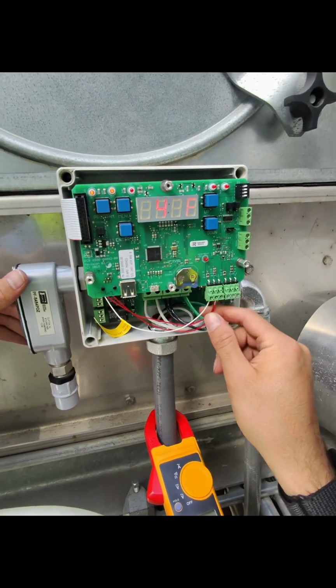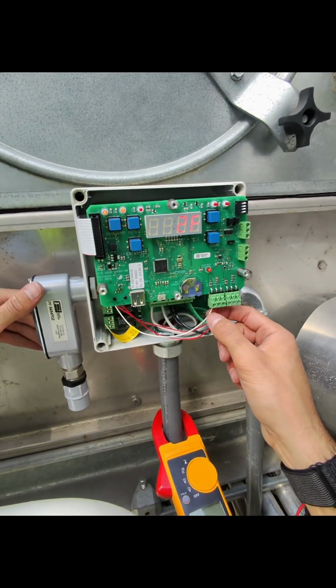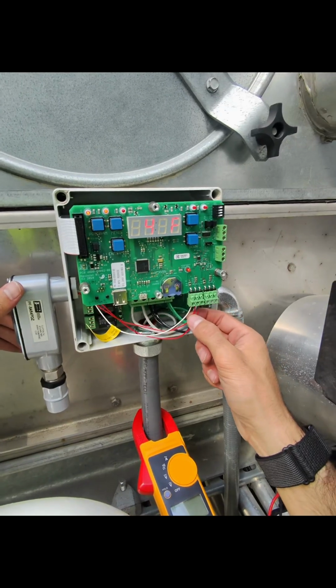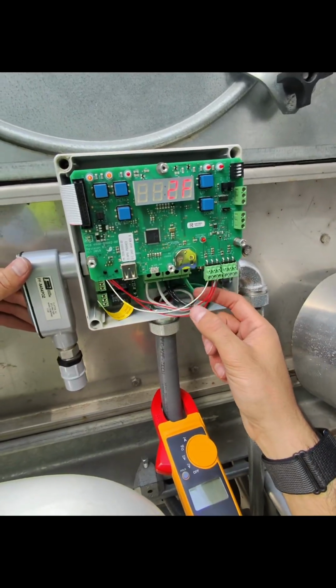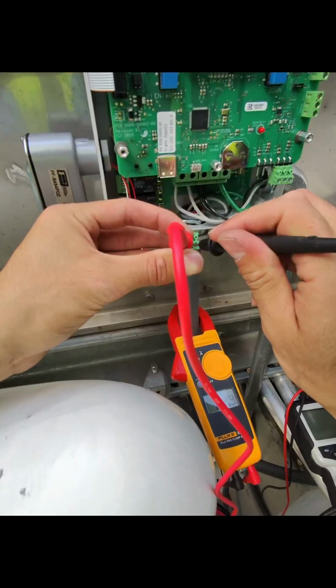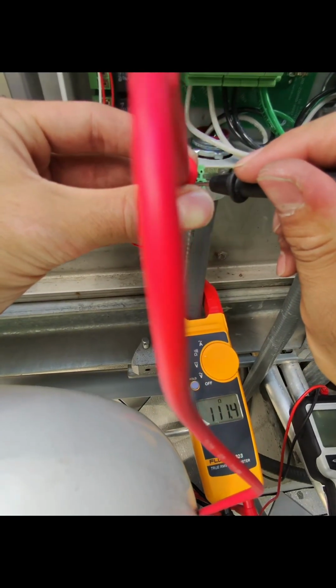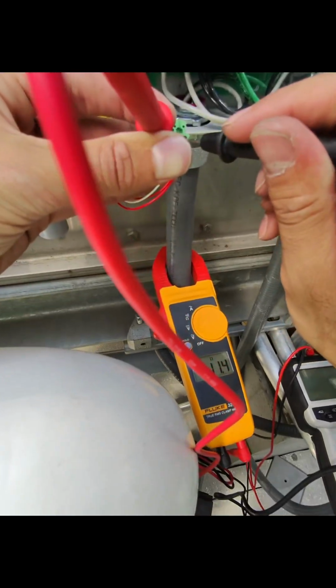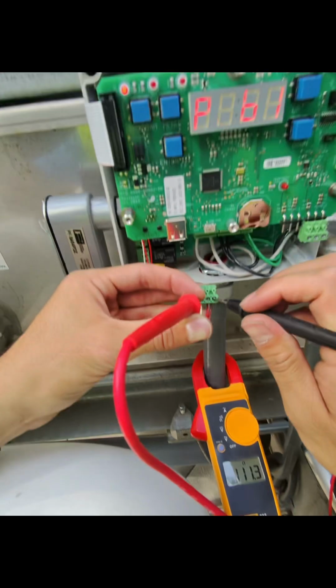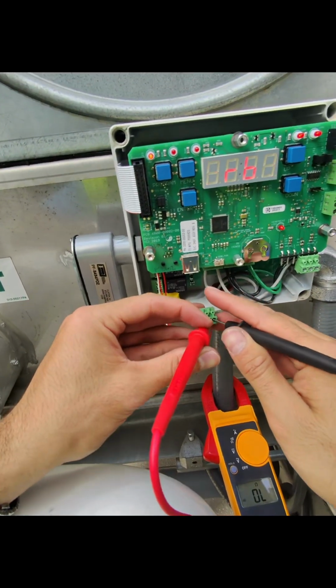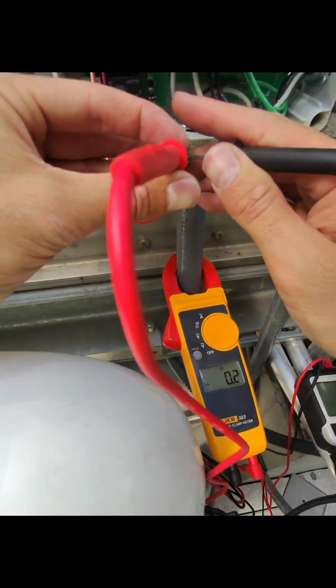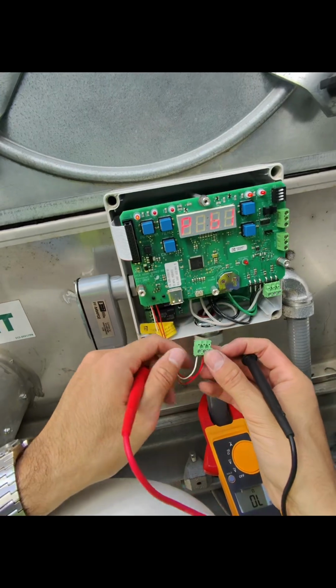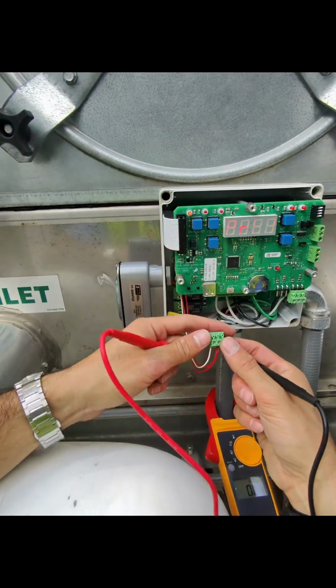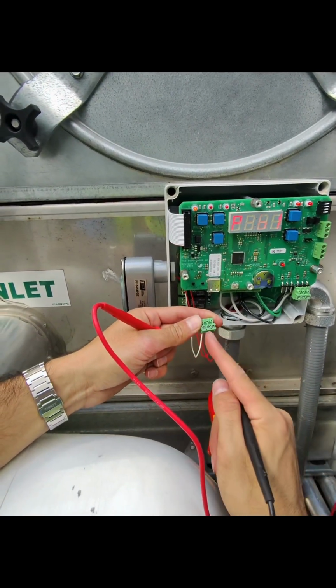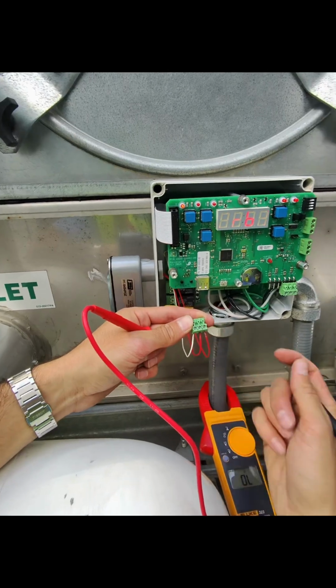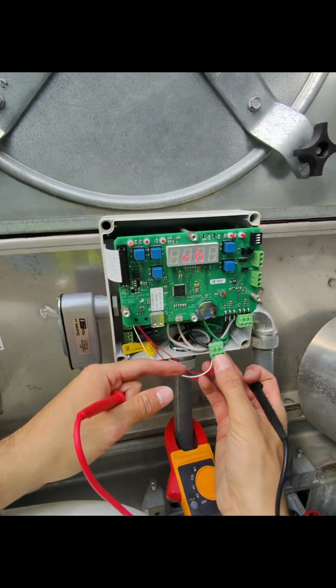The way you can test this, if your wires are not white, red, red, say you're using an extension wire or something similar, you would take a resistance reading. So from white to red, I get 111. From white to red, I get 111. And then from red to red, I get continuity, which is totally normal. The reds are interchangeable in this case, so if I switched this red over to the middle terminal and this red over to the outside terminal, I would still get a good reading.